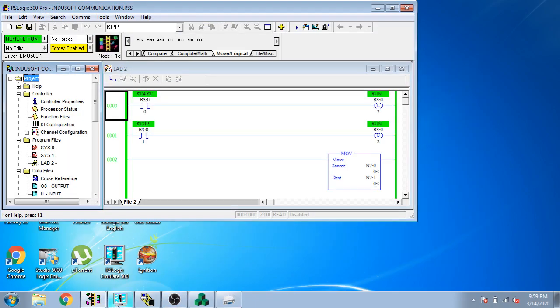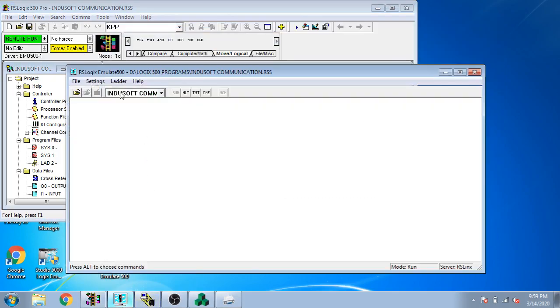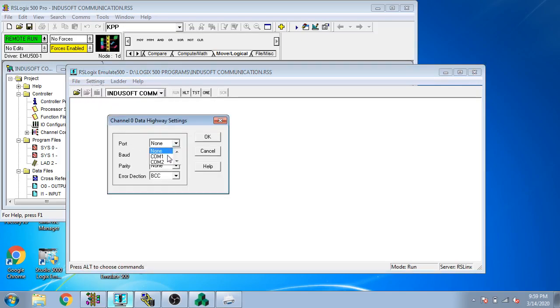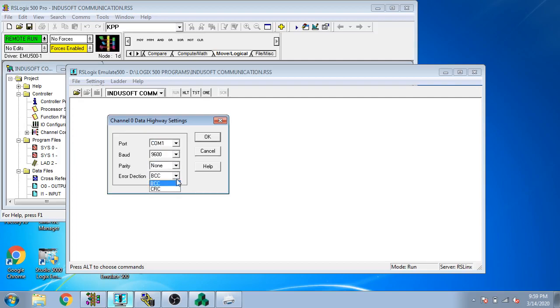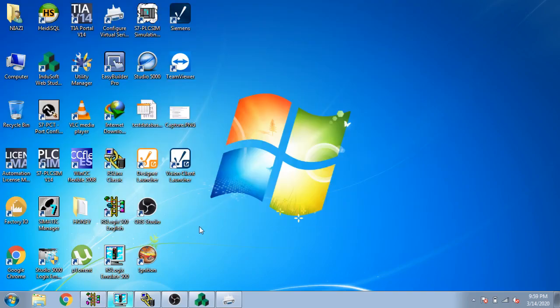My RSLogix 500 is now running — you can see it is running. I go to Settings, Channel Zero Data, and I am going to select COM1 and use 9600 baud. Parity is None and CRC for error check. I click OK.